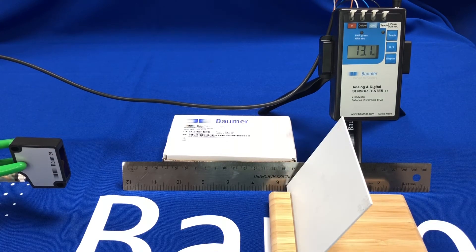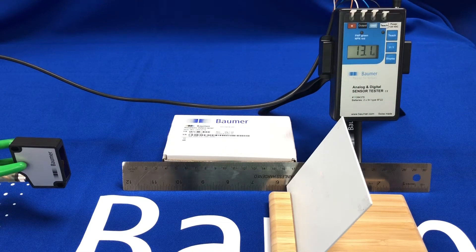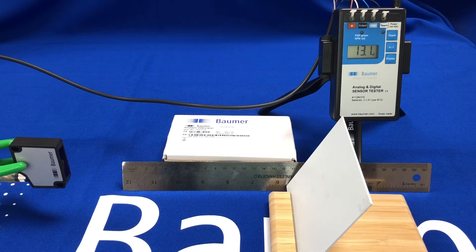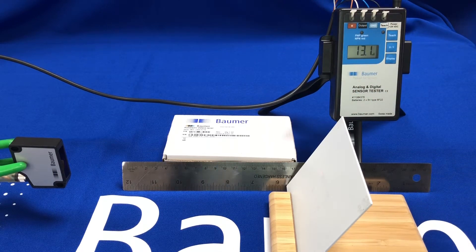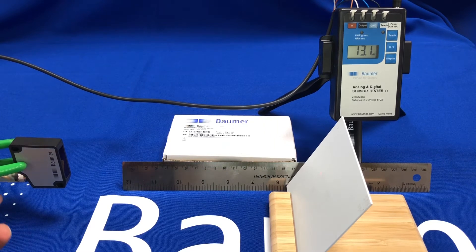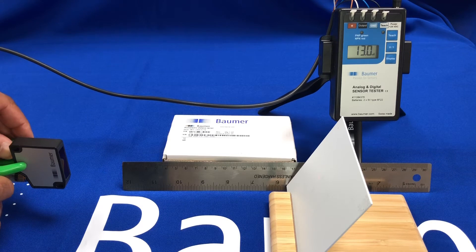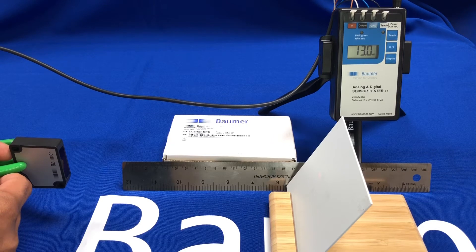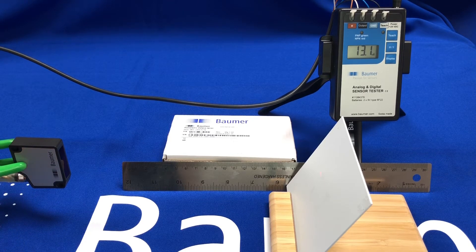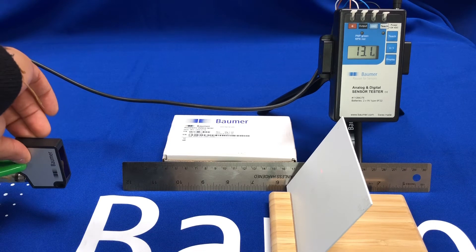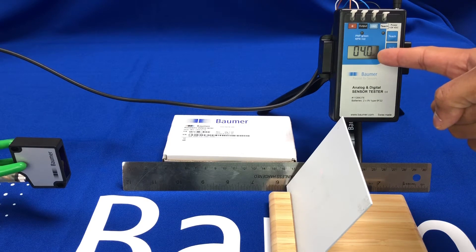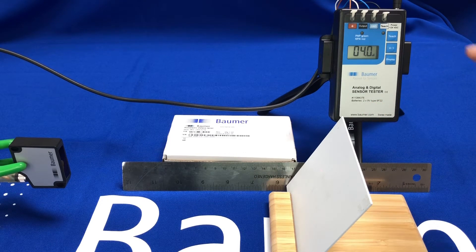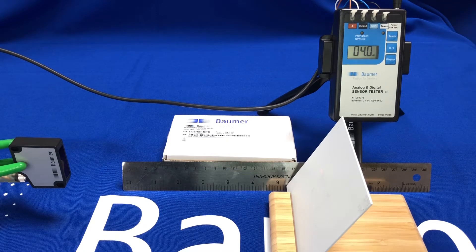The sensor can be set up to have a zero point anywhere within its range, and it's quite easy to do via IO-Link or just by the teach button at the back of the sensor. You'll see at this distance here we're getting around 13 milliamps. All I need to do to engage the teach is to press the button at the back, and then press and hold for two seconds. One, two, and you'll get some blinking on the back of the sensor. Then after those two seconds, press the button again briefly, and you can see now that it's set that as our zero point and the 4 milliamps is now showing. Previously 13 milliamps, now at this distance we've set our zero point on the analog signal, giving us 4 milliamps at that range.